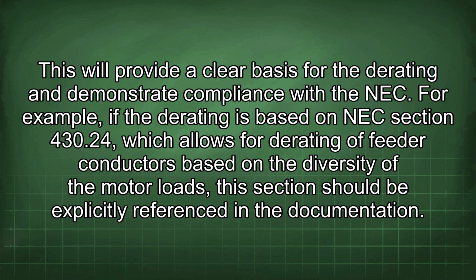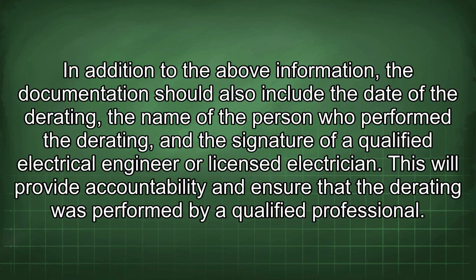For example, if the derating is based on NEC section 430.24, which allows for derating of feeder conductors based on the diversity of the motor loads, this section should be explicitly referenced in the documentation. In addition to the above information, the documentation should also include the date of the derating, the name of the person who performed the derating, and the signature of a qualified electrical engineer or licensed electrician. This will provide accountability and ensure that the derating was performed by a qualified professional.